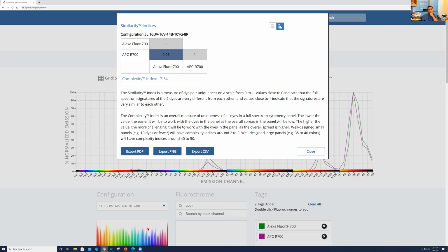Then the other question is, do the extra channels facilitate unmixing for close fluors if they bleed into them? I can answer that. Yes, absolutely. The more channels you have, they could be helpful. It doesn't mean they will, especially if the peaks are low, depending on the type of unmixing that is done. But I believe with Cytek's linear unmixing, the weight of the lower peaks is not as high as the higher peaks, but still it could facilitate, yeah.